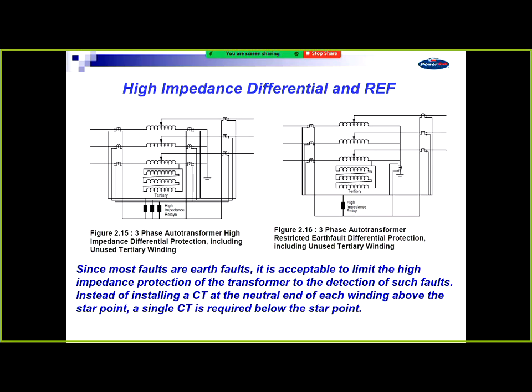So this is how you'd wire up your CTs. This is an auto transformer. You can see one winding in the middle, and then the tertiary is a delta winding. So what you've got on the left is a proper high impedance scheme. And you'll see going down the page, those solid ones there, that's the neutral, that's the star point, but we're above the star point in each of the phases. So that's why there's 3 of them. That's how you need to connect it.